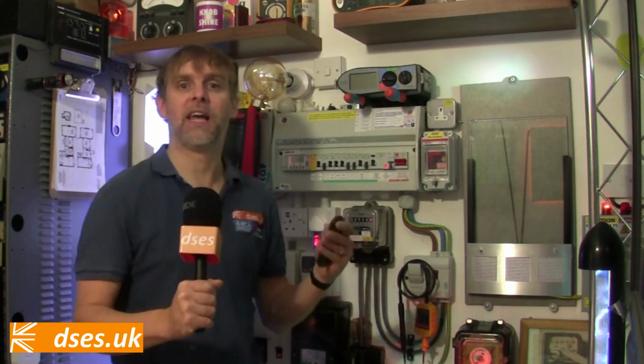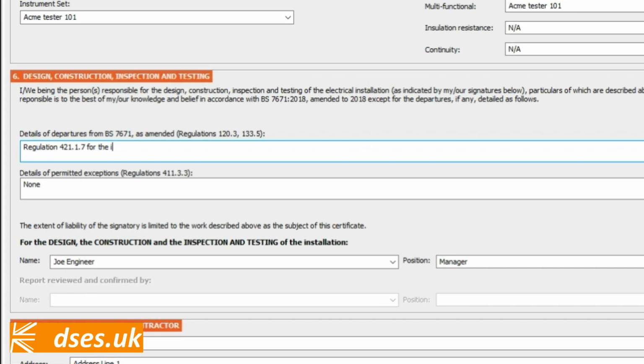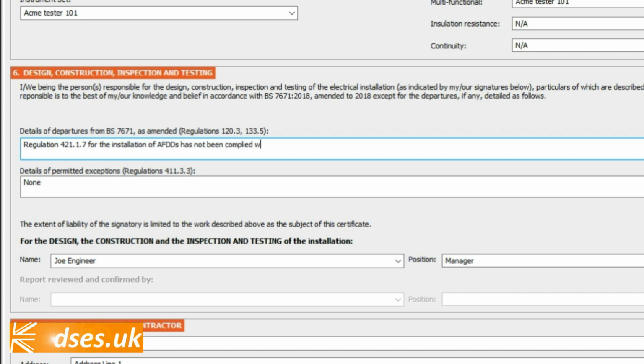These items will have to retail somewhere near today's RCBO prices if they're going to be viable from 2022, and manufacturers will be keen to get you used to their particular product, so let price wars commence. Otherwise, if this kit stays at today's price point, we're just not going to fit them, despite what 421.1.7 says. You know that details of departures field on the electrical installation certificate? We'll get used to writing regulation 421.1.7 for the installation of AFDDs has not been complied with as the client lacked suitable budget for the hardware, or words to that effect. In terms of population, I've seen comments recommending AFDDs or even RCBOs not being sited together in consumer units in case of a build-up of heat.